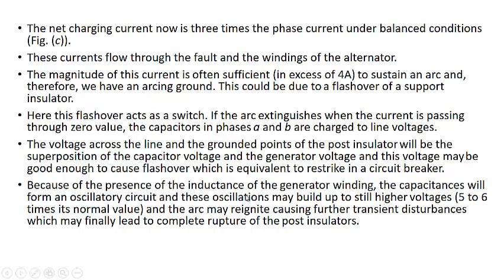Now, because of the presence of the inductance of the generator winding and the capacitance, they will form an oscillatory circuit, or resonating circuit. When these oscillations occur, they may build up a still higher voltage, 5 to 6 times the normal value, and the arc may reignite, causing further transient disturbances. The arc will reignite again, resulting in further disturbances, which may finally lead to the complete rupture of the post insulator. So this is very important. This arcing ground may result in high voltages. It results in continuous, or intermittent, arcing between the healthy phase and the ground, and finally it may result in the rupture of the post insulator.